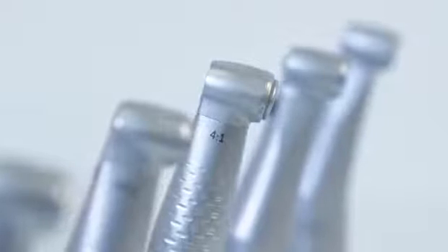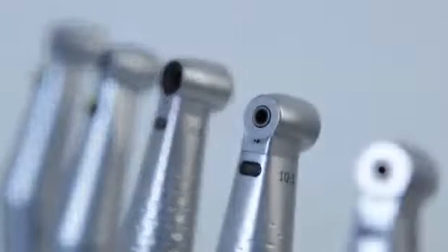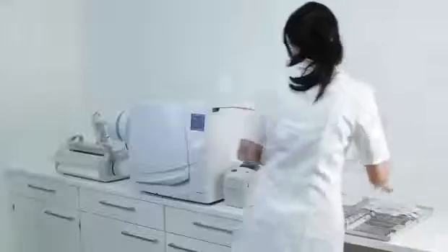Dental instruments need precision and have to be cleaned regularly. The Leaser 500 Fully Automatic autoclave is a type B water steam sterilizer that completes the perfectly secure hygienic program. It works with made-to-measure automatic type B cycles, saving time, water and energy according to the number and type of items. Combined with the patented water separation and filtering system, Leaser 500 is an economic solution for every practice.